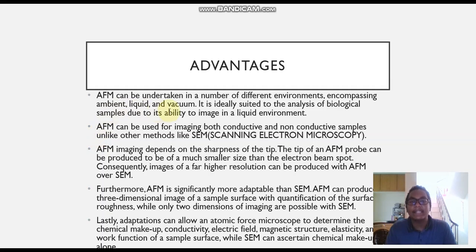When we talk about the advantages, it has a number of advantages compared to the nearest competitor it has, that is the scanning electron microscope. AFM can be used in a variety of environments encompassing ambient, liquid and vacuum. It is suited for analysis of biological samples also. Sorry, AFM can be used for imaging both conductive and non-conductive samples, unlike other methods like SEM. AFM depends on the sharpness of the tip. The tip of the AFM can be produced at a much smaller size than the nearest competitor, that is the SEM. So the smaller the size of the tip, the better the resolution.